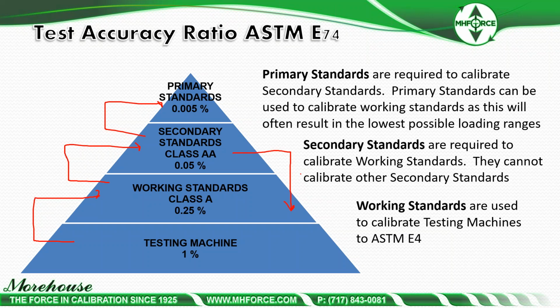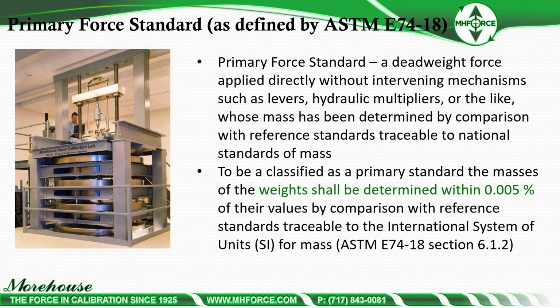What we cannot do, we cannot take that 2.25 million pounds and give a Class AA range, which is in here. No one in the world can give a AA range because it requires primary standards, and the largest machine is located in Gaithersburg at NIST, and it is a 1 million pound deadweight machine. Lots of recent articles about it. They're all great about how they recalibrated the weights, tore the machine apart. Really, really cool stuff. Anyway, so if we start going into this primary force standard, what is it?